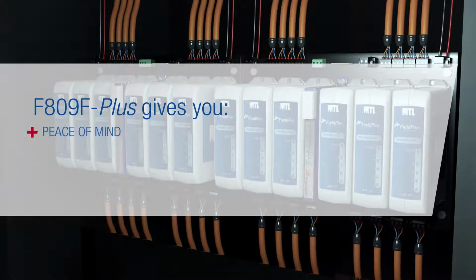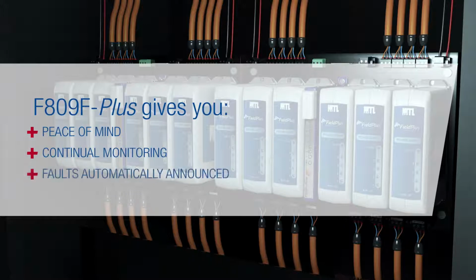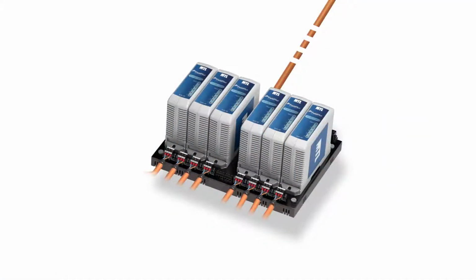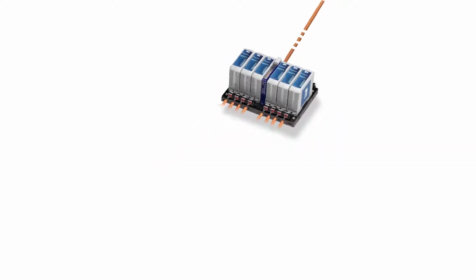MTL's F809F Plus gives you peace of mind that the health of your Foundation Fieldbus network is being continually monitored and that emerging faults will be automatically announced. The F809F Plus module is the only additional hardware you need to implement the physical diagnostic capability. It is simple to install and easy to configure. F809F Plus simply plugs into a dedicated slot on the module carrier for the Fieldbus power supplies, such as MTL's F800 and 9180 Series 8 segment units.